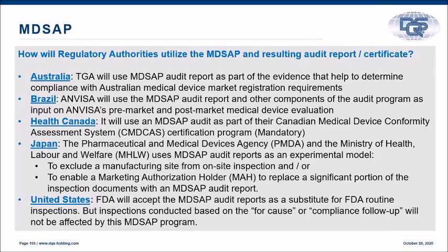How these regulators are using these MDSAP audit reports and certificates. So TGA, the regulatory authority for Australia, uses this MDSAP audit report as part of the evidence that helps to determine compliance with Australian medical device market registration requirements. So when you have to register a product in Australia, having an MDSAP report and certificate is an added advantage, though it is not mandatory. It is not mandated, it is preferred.